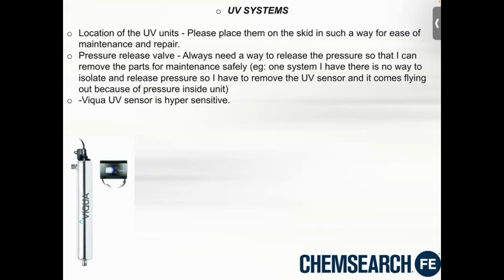And in regards to a specific brand of UV, everyone's probably seen the Viqua brand, and I am not a fan, to be honest. I feel it's more difficult than needed to do maintenance on these units. Sometimes it's the location of where it's placed on the skid, but the UV sensor on the Viqua brand in particular is hypersensitive. I've spoken to Viqua many times about how sensitive it is, and one rep admitted to me that yes, it is a little too hypersensitive for a reclaimed water application. I can put in a new quartz sleeve, new UV bulb, new UV sensor, and that sensor can go off in 48 hours. It's just sometimes too hypersensitive.